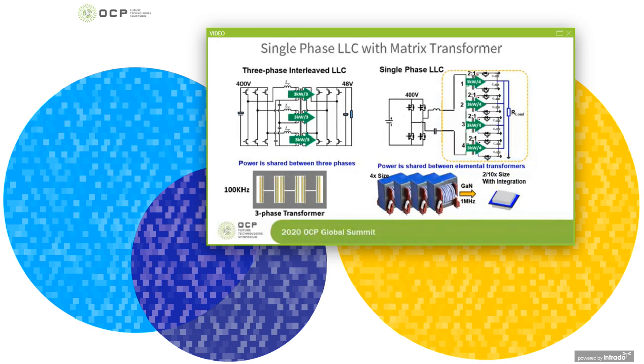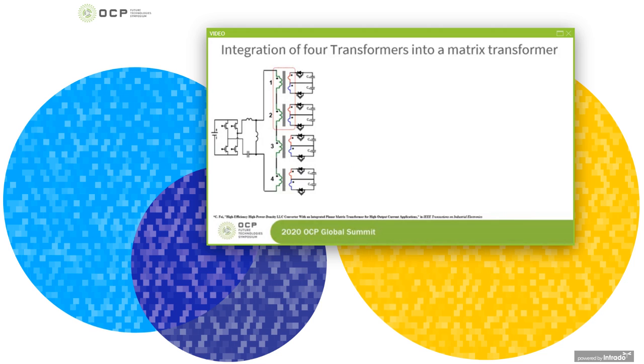Here's how to integrate 4 transformers into one matrix transformer core. Looking at the first 2 transformers, we can use a UI core, where each leg of the UI core is basically one transformer with perfectly interleaved primary and secondary windings.